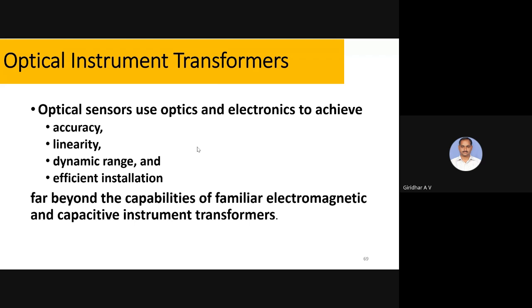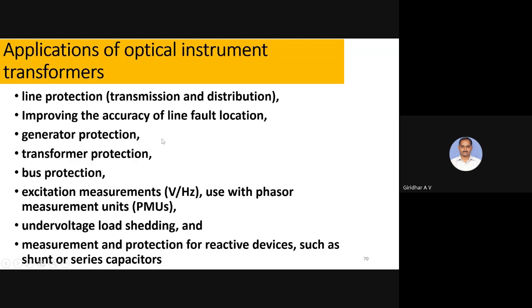These optical transformers are finding applications nowadays in line protection, transmission and distribution, improving the accuracy of line fault location, generator protection, transformer protection, bus protection, excitation measurements, along with phasor measurement units, and also under voltage load shedding, and measurement and protection for reactive devices, shunt and series capacitors. So it will find applications.